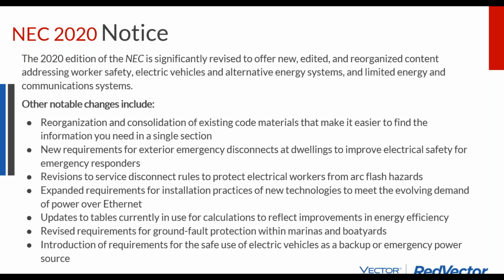And in many jurisdictions the tide was kind of turning in that favor, and many were getting rid of their local exterior disconnect switch requirement. And now NEC 2020 comes back and says, well, it's part of the National Electric Code now, so you have to have this exterior switch. And at any rate, once you get above a certain voltage level, the switches have more requirements, but let's just leave that for now. The exterior disconnect switch, commonly a knife switch, is now mandated in electric code.